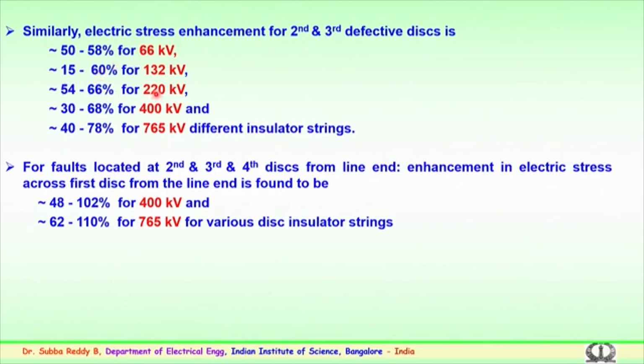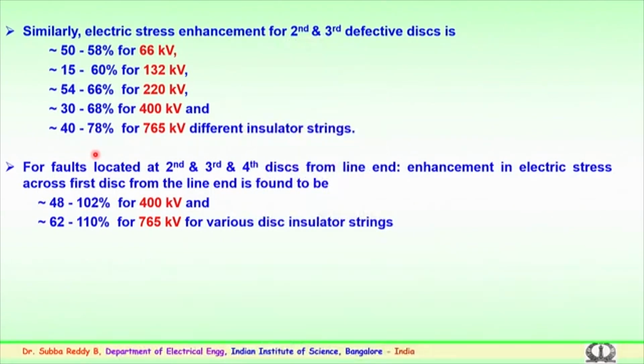For 220 kV, where there could be 13 to 15 discs, if there are faults on the second and third, the rise in electric stress faced by the first insulator could be 66%. Similar stress for 400 kV, and anywhere from 40 to 78% in case of 765 kV. So, you can see that compared to normal conditions, if the second or third disc is faulty, the stress increases. This increase in stress, again because of contamination or fog, could have a much greater effect, and finally the failure of the insulator string could happen.